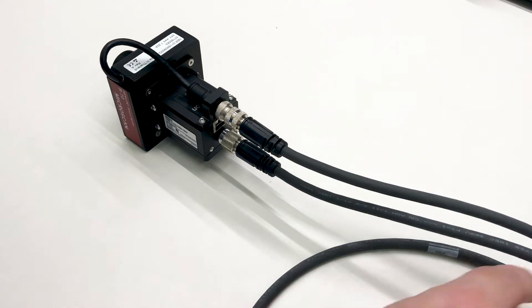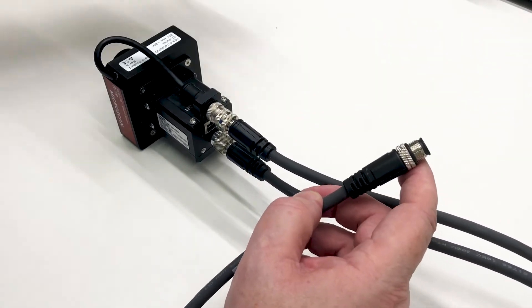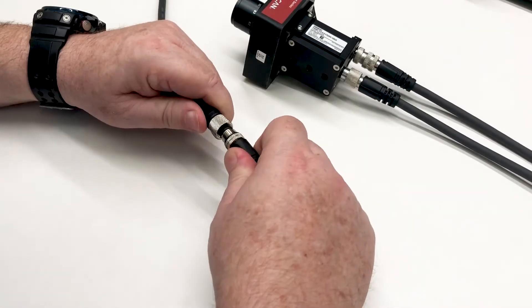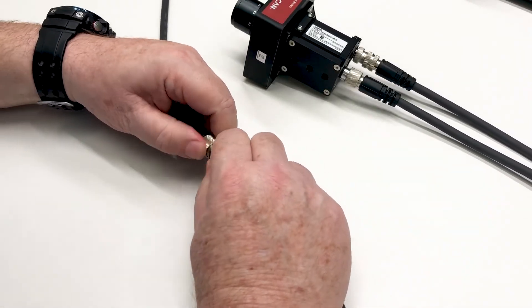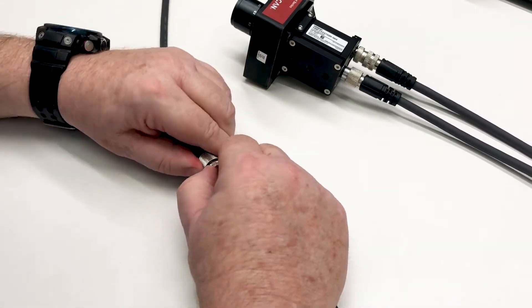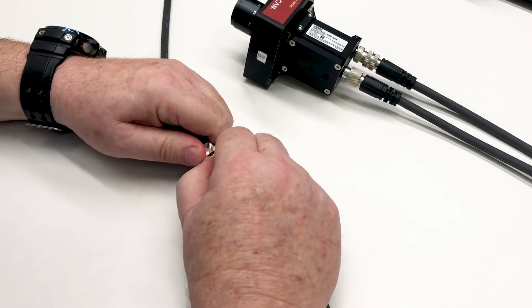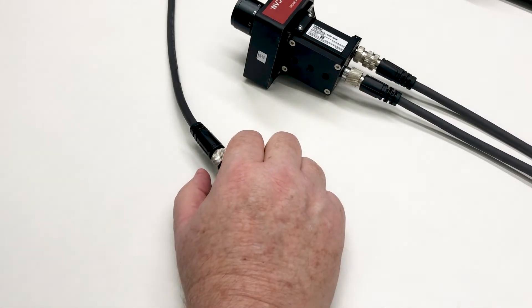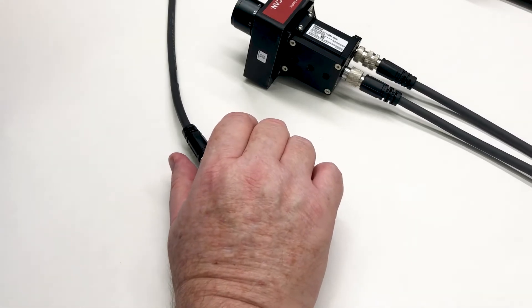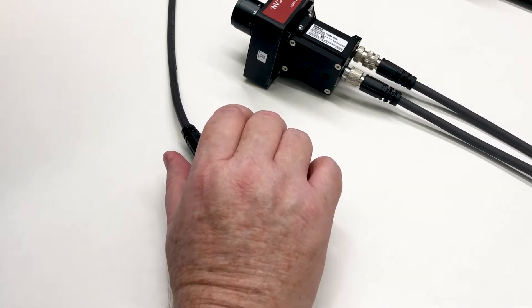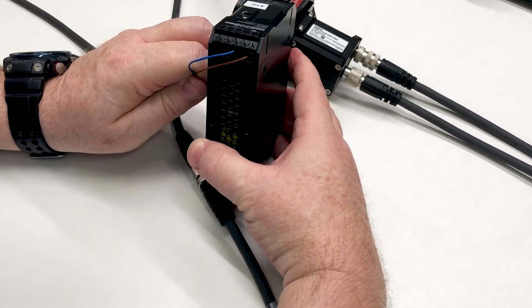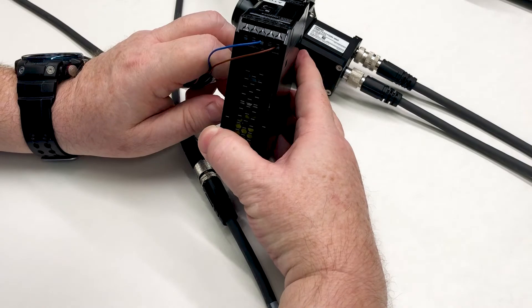Okay, now you attach your flying lead cable to your Y cable. And same thing, you rotate until you feel it meets up and then screw in. And the other end of your flying lead cable you want to connect your brown wire to the positive 24 volt supply and the blue wire to the negative.